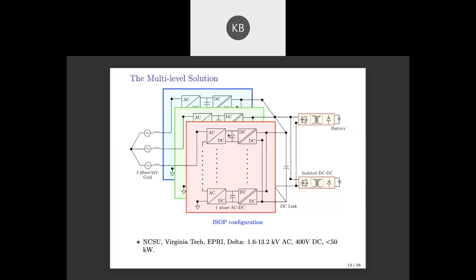Then on the AC side, because it is medium voltage, you connect them in series, and on the DC side, you parallel all these converters, making a common DC bus. This is basically the idea, called a multi-level input series, output parallel configuration.